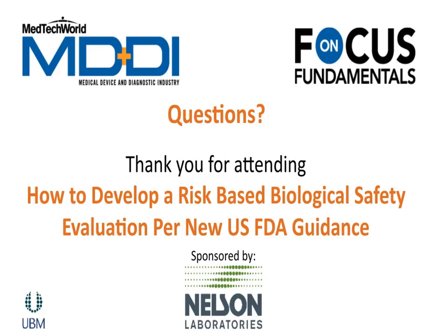Okay, great. Good to know. So we have one. What is the criteria used for determining a worst case for colorants in materials? Okay, so a worst case for colorants. When I gave the example for the catheters, the worst case product was to combine and make sure we included all the different colorant options.